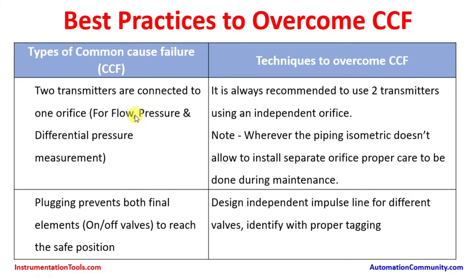Two transmitters connected to one orifice — used for flow, pressure, and differential pressure measurement — can lead to choking affecting both instruments. It is always recommended to use two transmitters with independent orifices. However, if the piping isometric does not allow separate orifices due to space and distance limitations, proper care must be taken during maintenance to isolate the correct instrument.